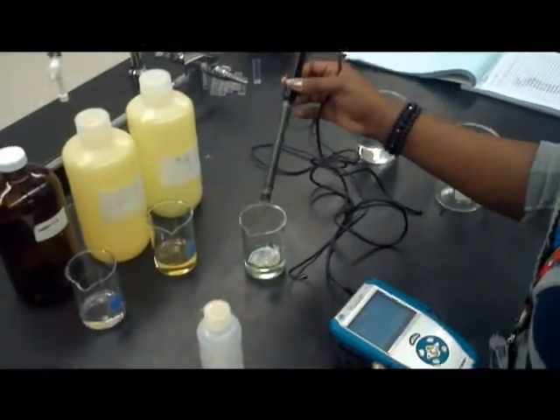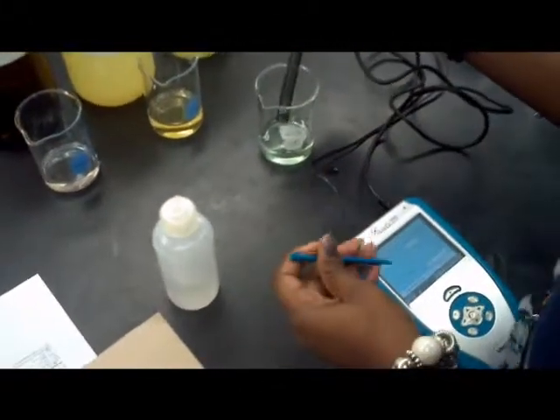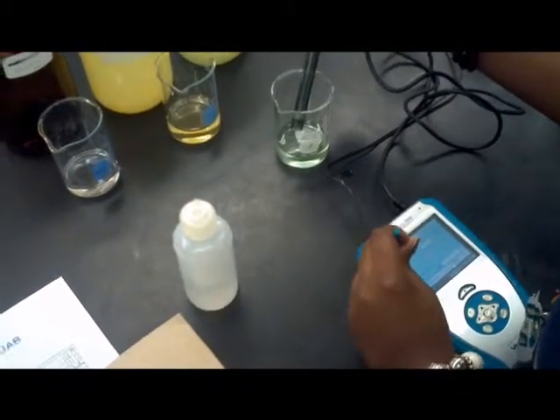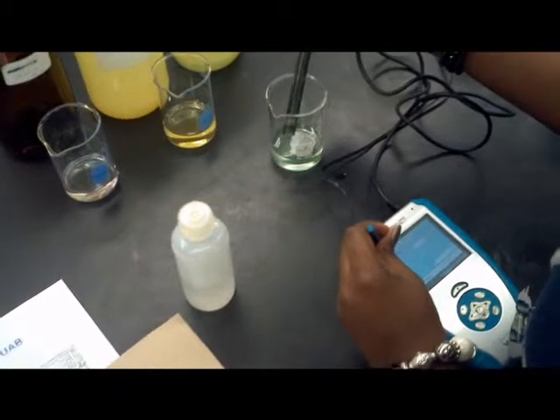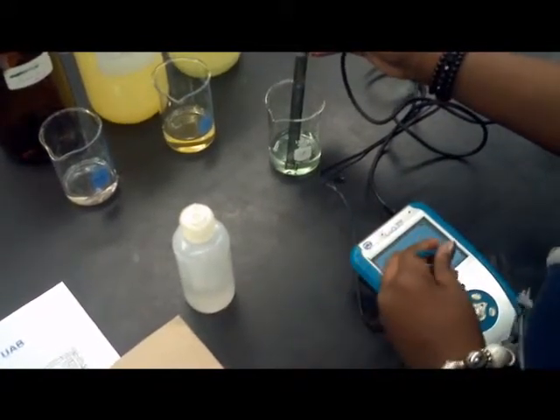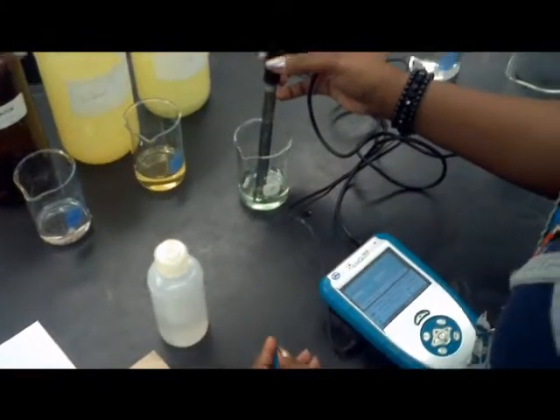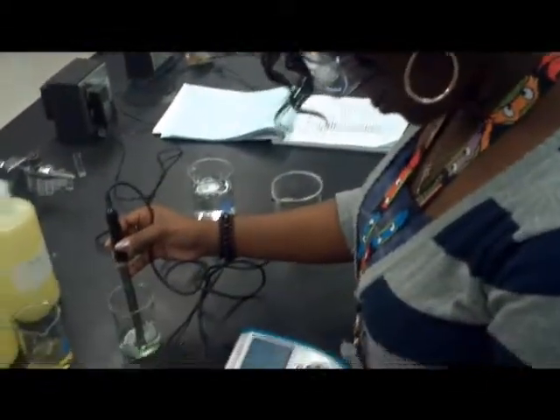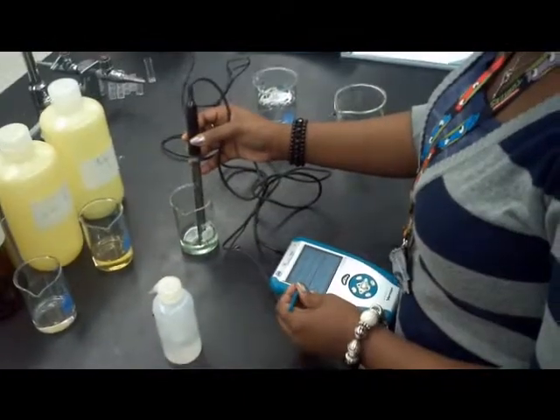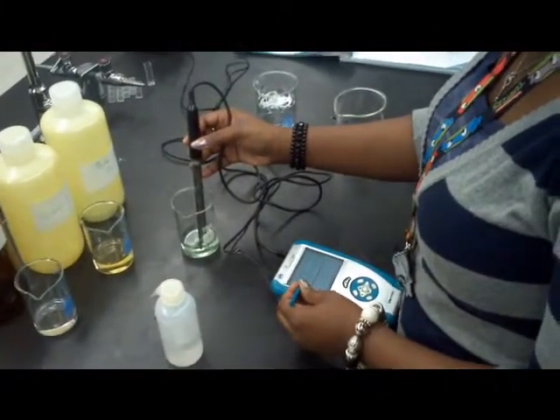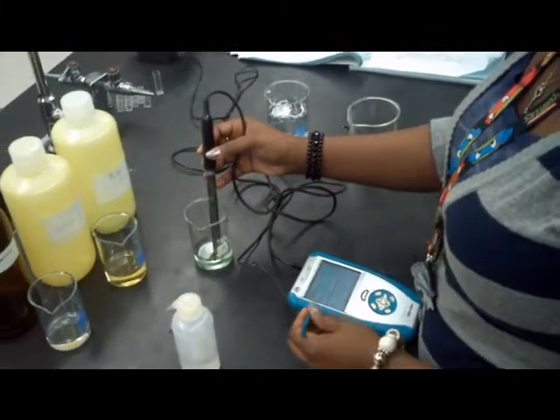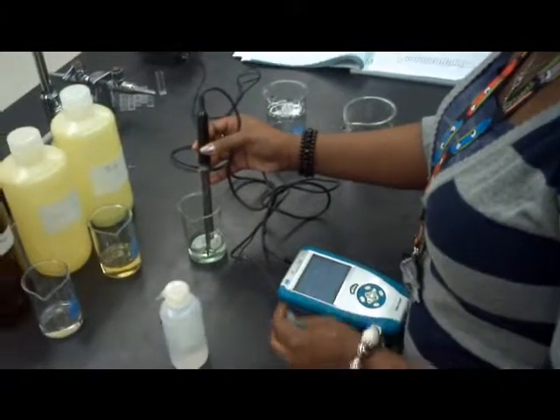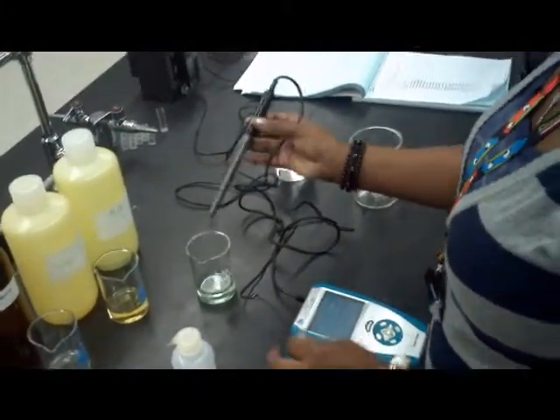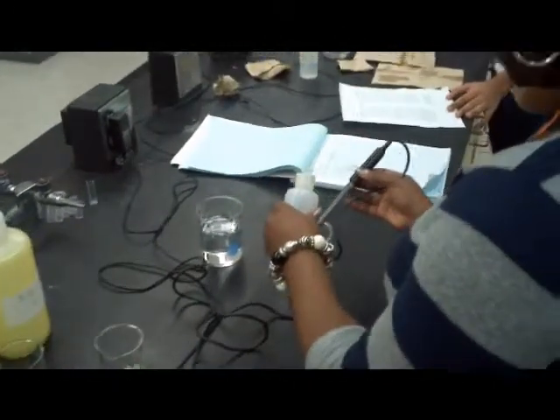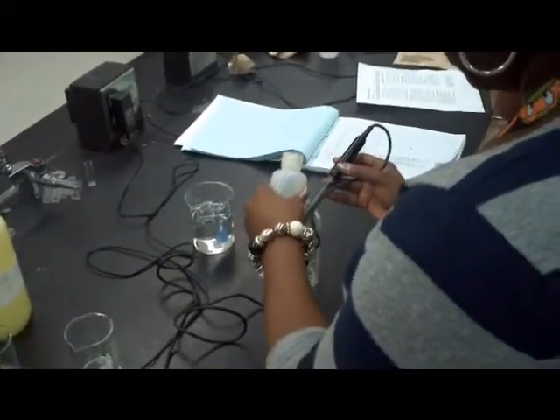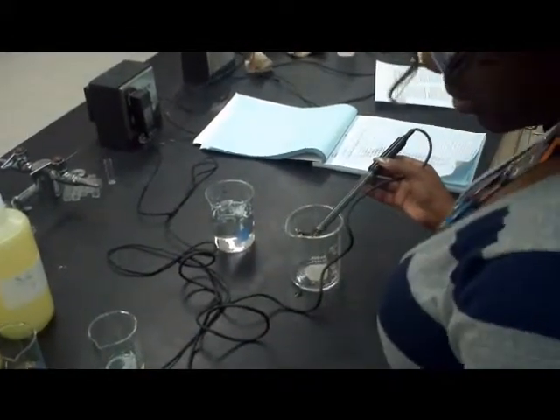Next, the probe needs to be placed into the buffer solution with a known pH of 7. Then input 7 on the pH meter so it knows what it is reading voltage-wise. Once the voltage has stabilized, hit the key under the number value and remove the pH probe from the solution. The probe needs to be rinsed off again and placed back into a wet solution if not in use.